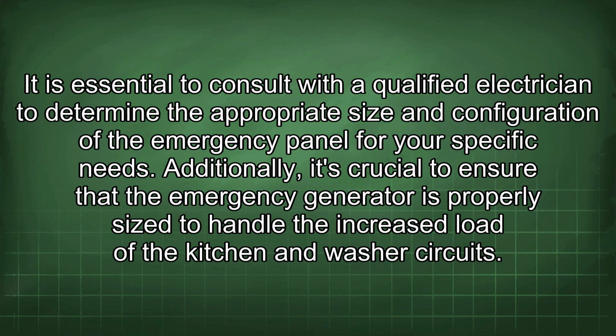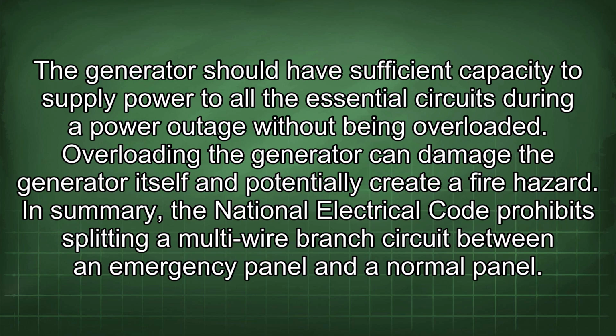Additionally, it's crucial to ensure that the emergency generator is properly sized to handle the increased load of the kitchen and washer circuits. The generator should have sufficient capacity to supply power to all the essential circuits during a power outage without being overloaded. Overloading the generator can damage the generator itself and potentially create a fire hazard.